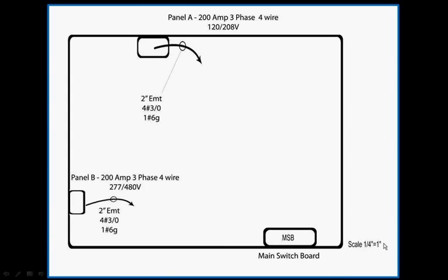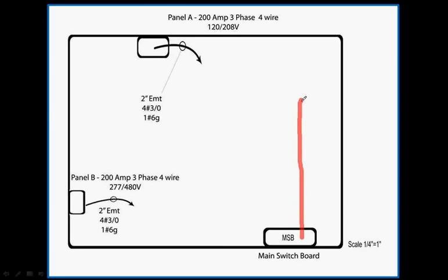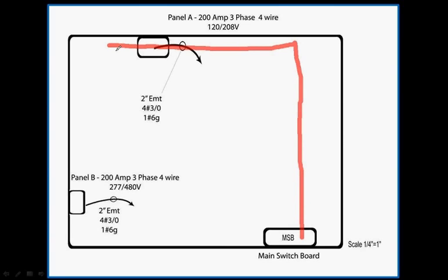Since both conduits on this drawing are the same size and conduit size and type, and the same conductor size and number, I can take them off and enter them into Red Rhino together with one entry. I will take off the conduit at right angles to allow enough conduit and wire to go around obstacles or obstructions of the building, and I also allow for conduit riser length by over rolling past the end of the conduit run. When you roll past, it adds extra length on the scalex count.